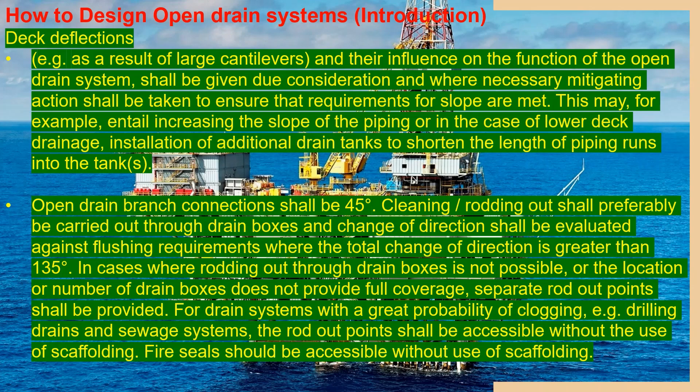Open drain branch connections shall be 45 degrees. Cleaning or rodding out shall preferably be carried out through the drain box, and changes of direction shall be evaluated against flushing requirements where the total change of direction is greater than 135 degrees.